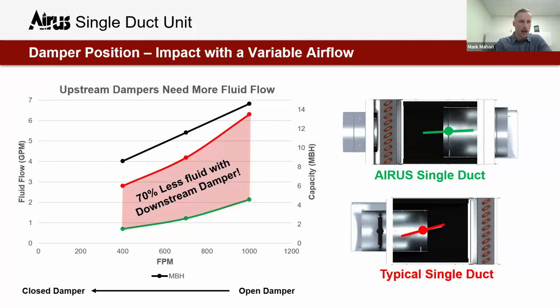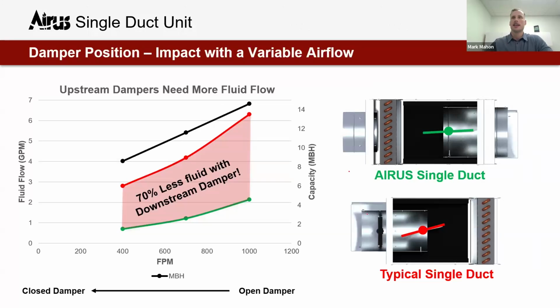I did see here from Matt, how's the configuration of the integrated actuator and valving setup with an inverse box like this? So one other thing I'd like to note here, the original patent drawing is not representative of the final assembly. What we can actually see for this product is, I'll draw the control box here. A control box for a traditional single duct would exist here. The control box for the new single duct would exist here. It's shifted slightly, but it's the exact same size, has the same clearance for DDC controls to be mounted, and is still in the same orientation, right hand, left hand, top or bottom, depending on however a design engineer designs it and a contractor purchases it.